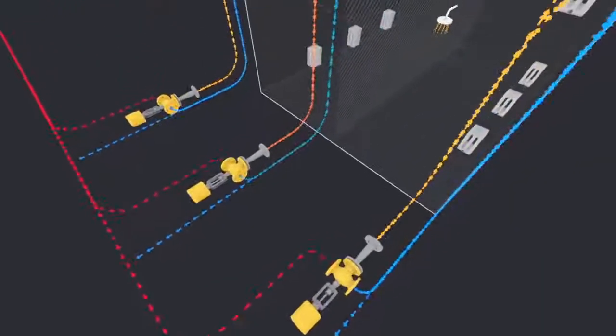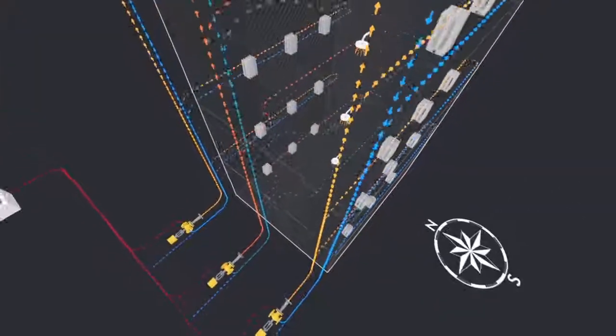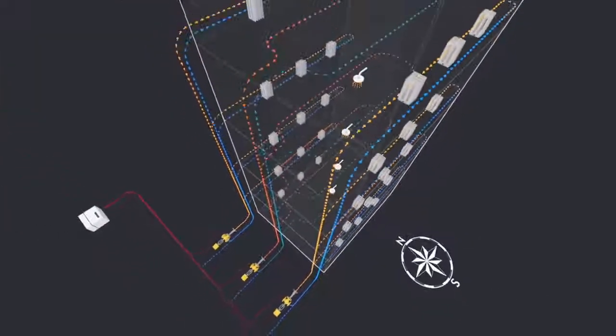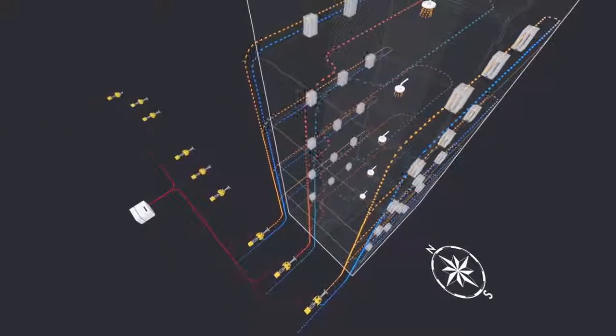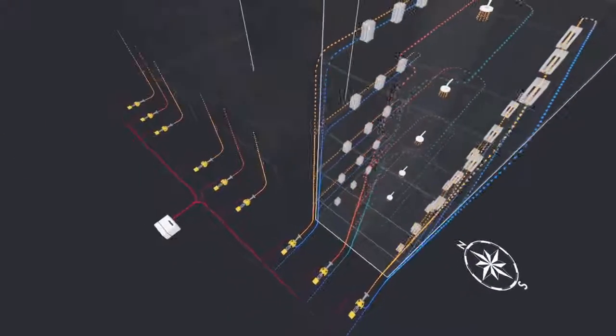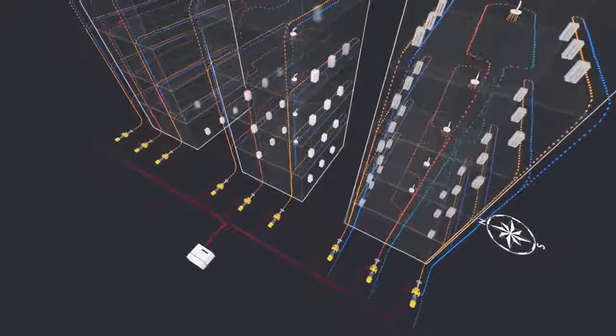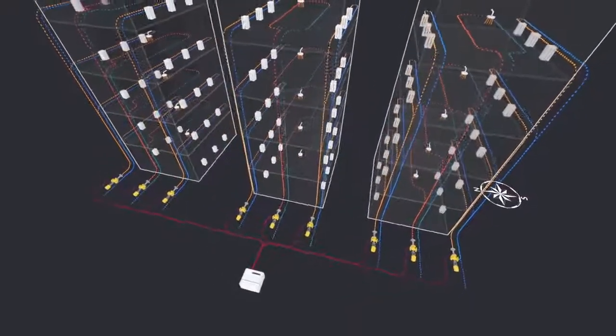In this application, the ejector replaces both the mixing valve and the electric circulator pump at the heating manifold. No flow energy is lost in the Jetomat Ejector. This system enables a main central pump to supply multiple heating circuits simultaneously.